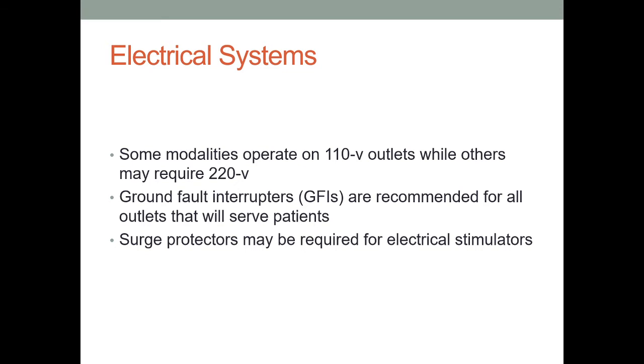You have to reset the GFI by pressing in and holding, I believe, the black button till that goes through. So you should check the GFIs regularly as part of your treatment. And if you were doing, say, a mock assessment with the BOC, one of the things that you would do as part of your pre-application components would be check the electrical system with the GFI. One thing that we probably should be adding to your checkoffs as you go through is a GFI check.